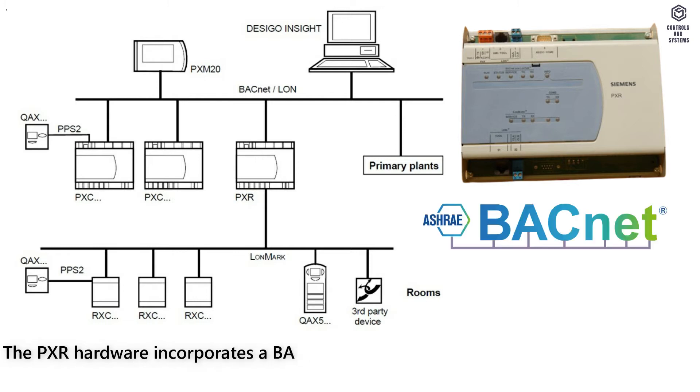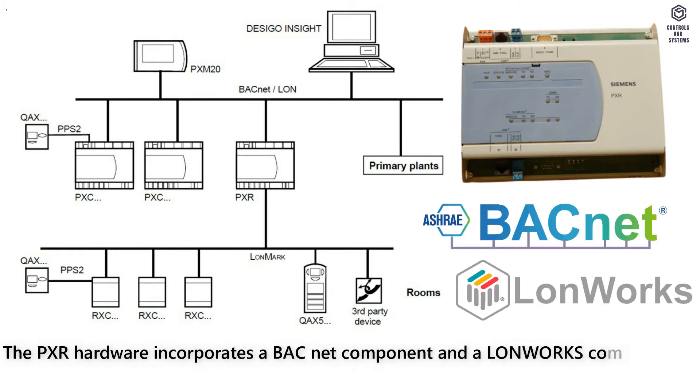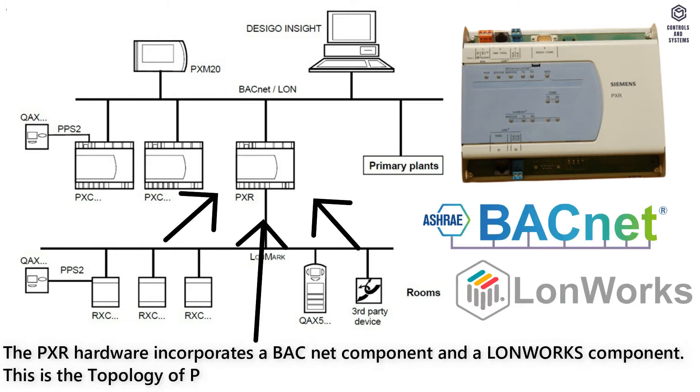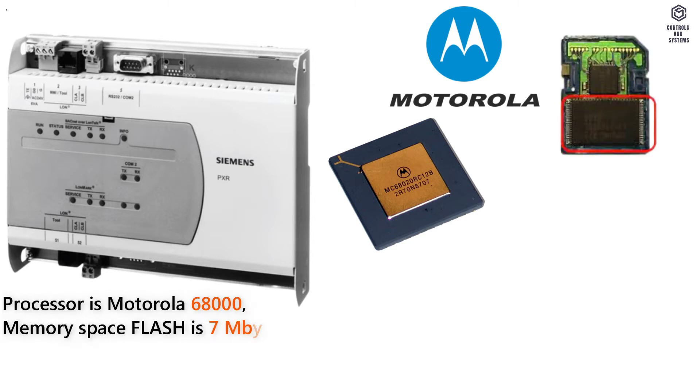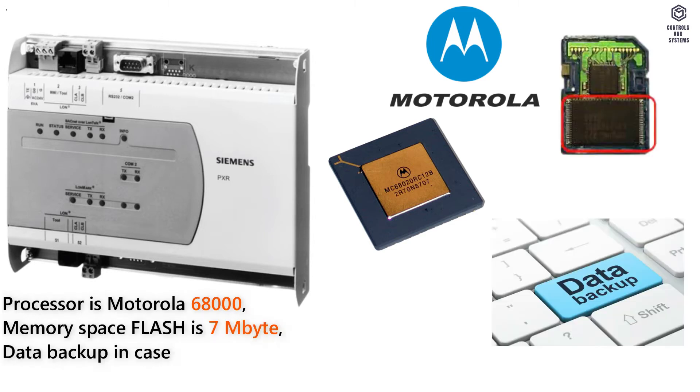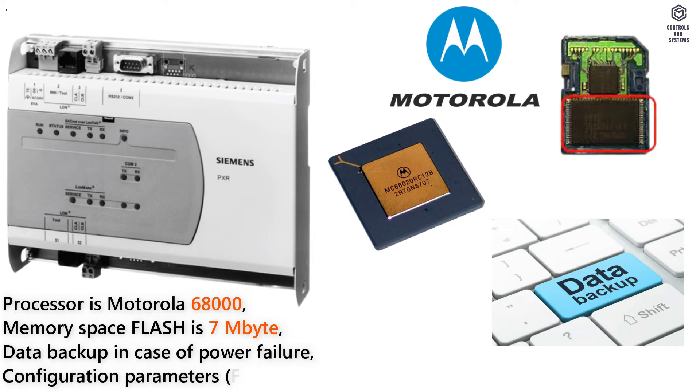Hardware. The PXR hardware incorporates a BACnet component and a LonWorks component. This is the topology of the PXR series controller. The processor is Motorola 68000, memory space flash is 7 megabytes, data backup in case of power failure for configuration parameters via flash is greater than 10 years.